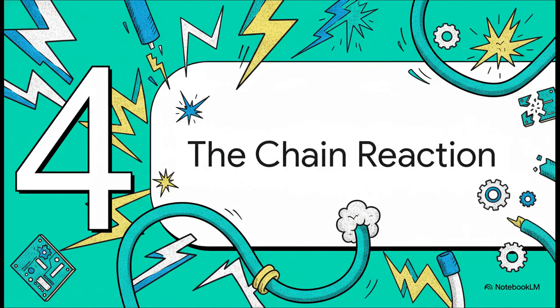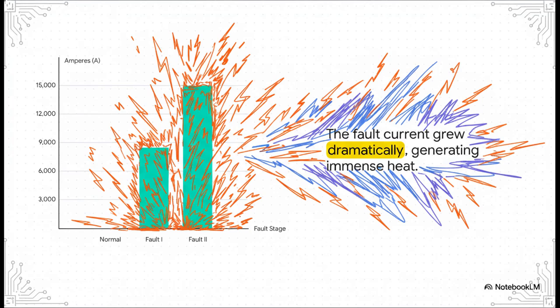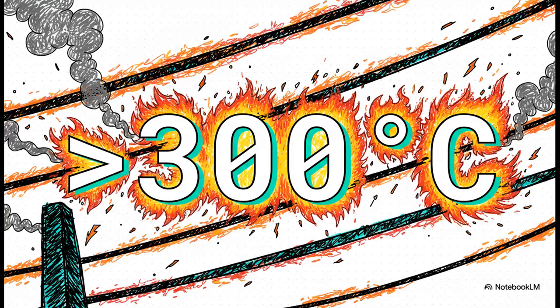short. And this is where the laws of physics just take over. When you pump thousands and thousands of amps into a system with no way of shutting it off, the consequences become very dramatic and very destructive. This chart really gives you a sense of the raw power involved. The first short circuit, fault I, was already pulling about 8,500 amps. But as things escalated, the current jumped to a staggering 15,000 amps. All of that current generates an incredible amount of heat. These high voltage lines, which are designed to operate at a maximum of 80 degrees Celsius, heated up to over 300 degrees. They were literally glowing and smoking as the grease inside them started to burn off.